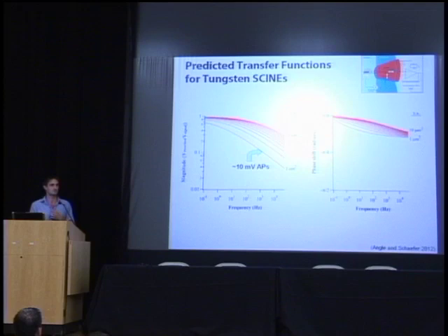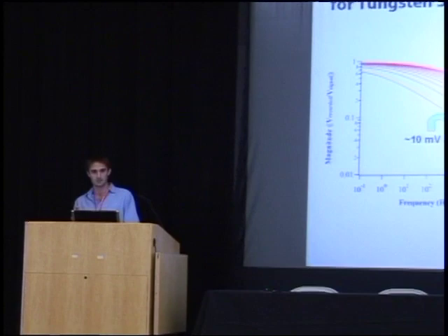And I think, really quickly, something that I heard people talking about yesterday, and I just wanted to touch on this thread: a lot of electrophysiologists are concerned about distortions. They're always fiddling with their capacitance compensation knobs because they want their action potentials to be a full 100 millivolts. But I think now with digital processing being as good as it is and with deconvolution techniques, it's relatively pointless to try to optimize the response of your electrode through these kinds of feedback techniques, because you can always deconvolve either on the fly using some kind of FPGA or post hoc. That's one aspect where I think that advances in signal processing have really changed the strategy for something like designing the electronics of amplifiers. It can be a lot simpler now.